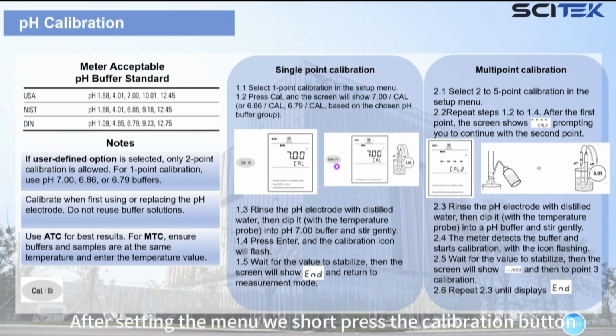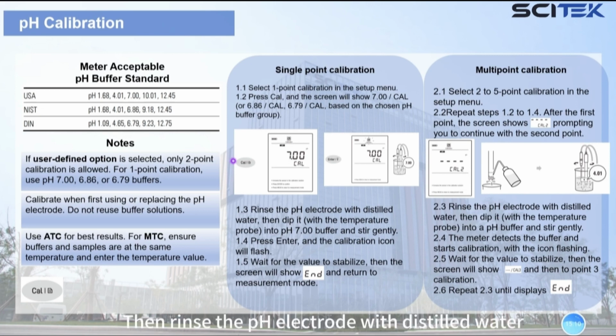After setting the menu, we short press the calibration button and then rinse the pH electrode with distilled water. Then dip it into the pH buffer solution and stir gently. Then press enter, this button, and the calibration icon will flash. Wait for the value to stabilize, then the sequence will end and return to measurement mode. The calibration is completed. When calibrating, the electrode and the temperature probe both need to dip into the pH buffer solution, like this picture.